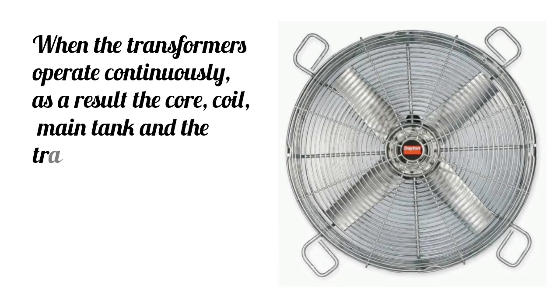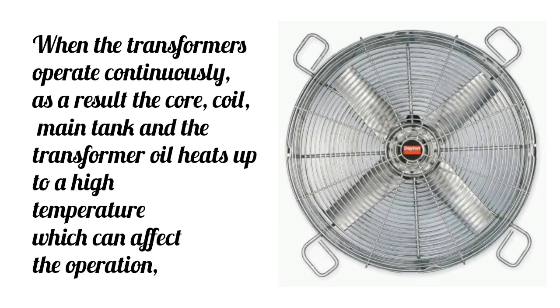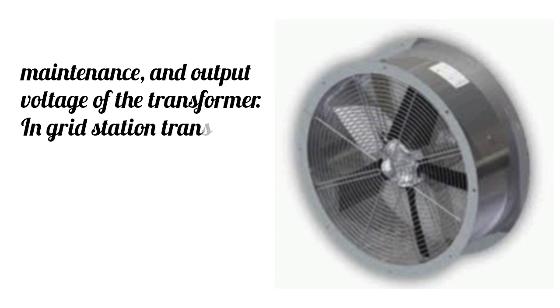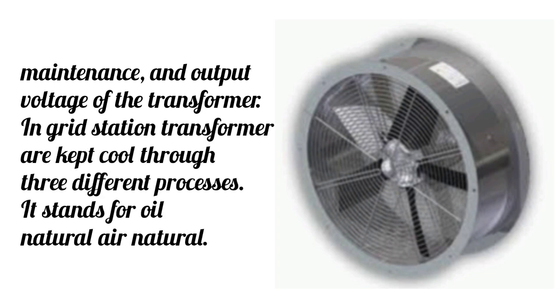Cooling fan. When transformers operate continuously, the core, coil, main tank and the transformer oil heat up to a high temperature, which can affect the operation, maintenance and output voltage of the transformer. In a grid station, transformers are kept cool through three different processes.